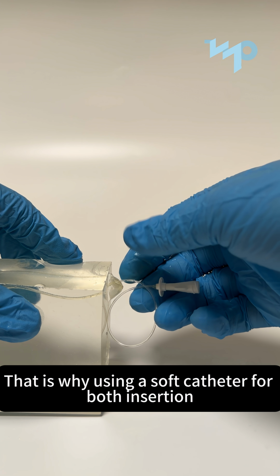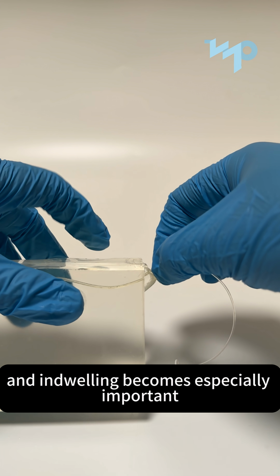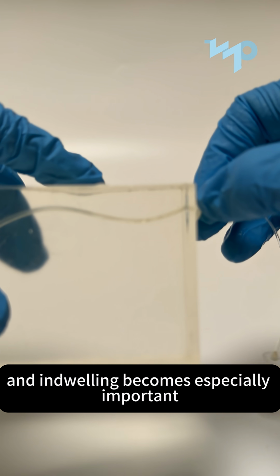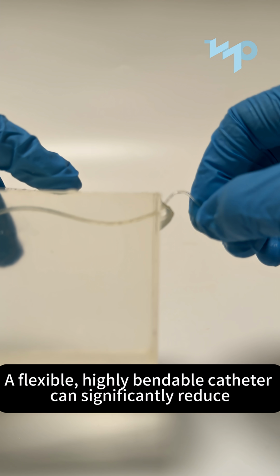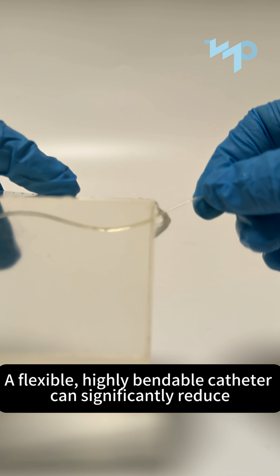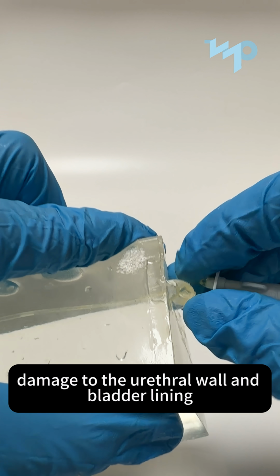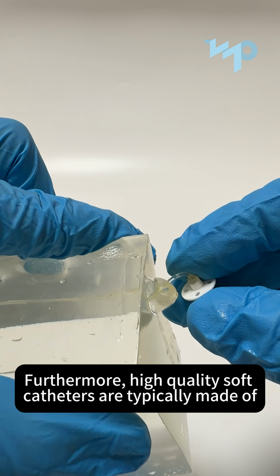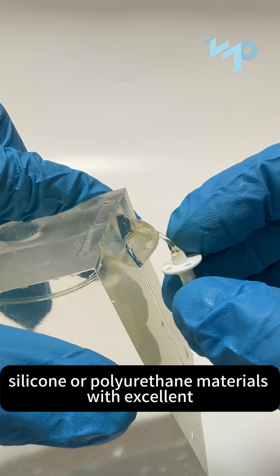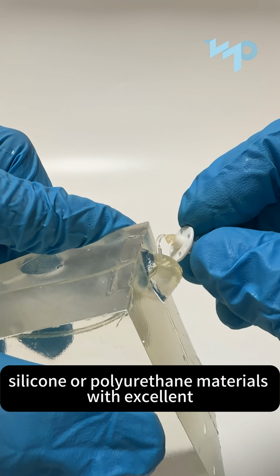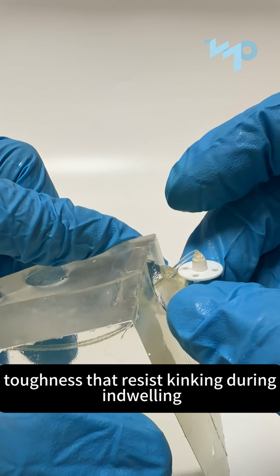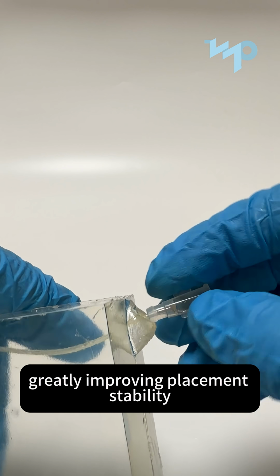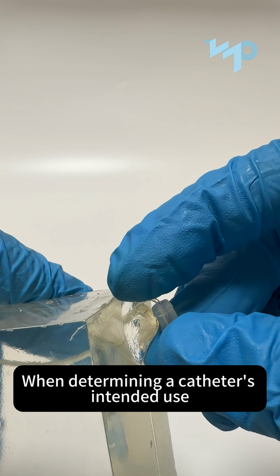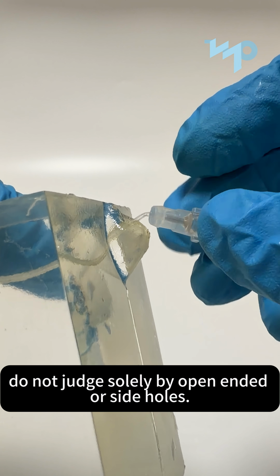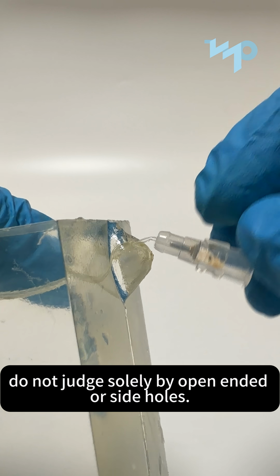That is why using a soft catheter for both insertion and indwelling becomes especially important. A flexible, highly bendable catheter can significantly reduce damage to the urethral wall and bladder lining. Furthermore, high-quality soft catheters are typically made of silicone or polyurethane materials with excellent toughness that resist kinking during indwelling, greatly improving placement stability. When determining a catheter's intended use, do not judge solely by open-ended or side holes.